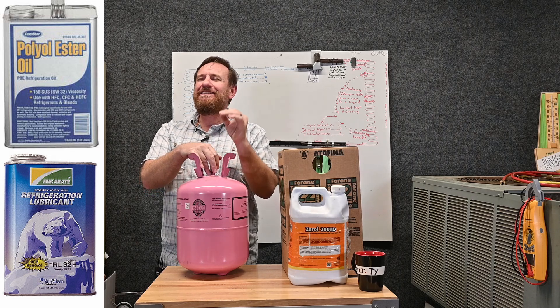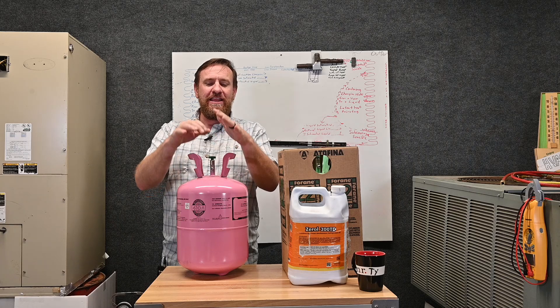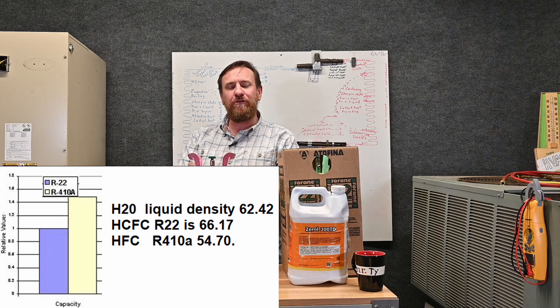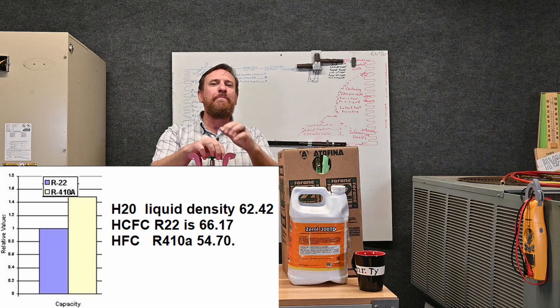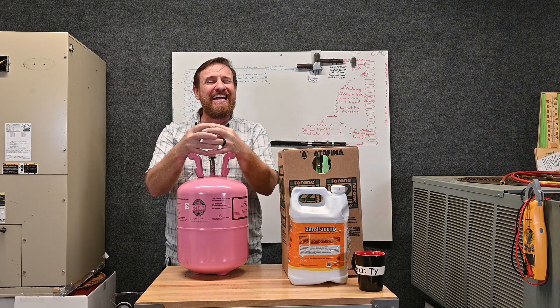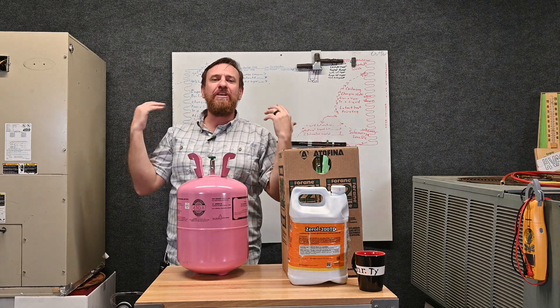I need to make something very clear. Just because R-410A is replacing R-22 doesn't mean you just take one out and put the other in — it replaces it by replacing the entire system. This refrigerant is entirely different. It has a different weight, it absorbs a different amount of BTUs per pound as it changes state. Because it has a different weight, it absorbs heat differently and has different properties. The compressor moves a different amount of refrigerant — an R-22 compressor is larger, while the R-410A has a smaller compression size.